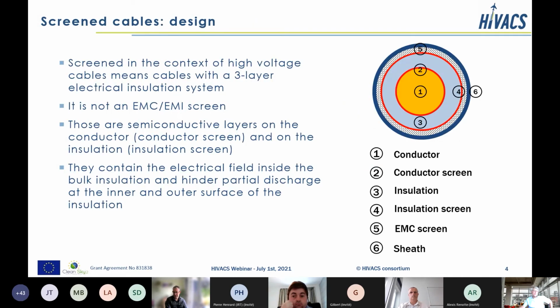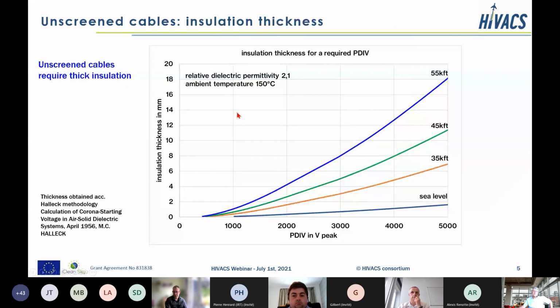Screen cables in the context of high voltage cables means it's not related to an EMI screen, but it means that we have a 3-layer insulation system where we have a first semiconductive layer on the conductor screen, and then a second semiconductive layer on the insulation screen. And those semiconductive layers contain the electrical field inside the bulk insulation. If we do not use screen cables, we will need relatively thick insulation for the unscreened cables.